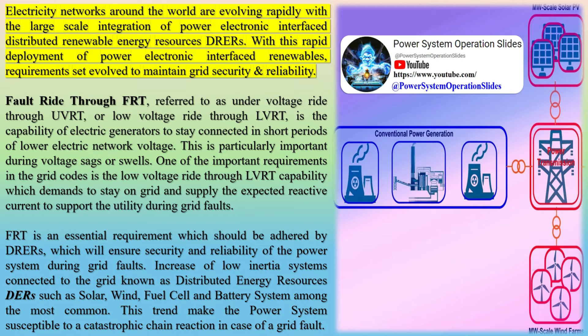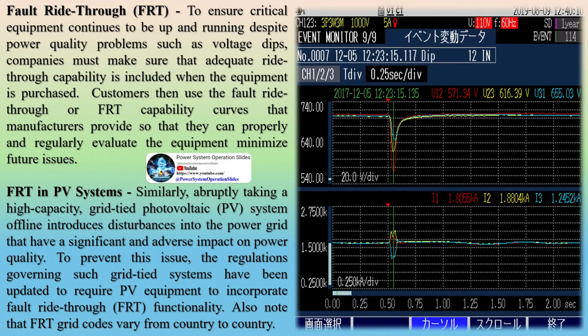Fault Ride-Through (FRT), referred to as Under-Voltage Ride-Through (UVRT) or Low-Voltage Ride-Through (LVRT), is the capability of electric generators to stay connected during short periods of lower electric network voltage. This is particularly important during voltage sags or swells. One of the important requirements in the grid codes is the LVRT capability, which demands staying on grid and supplying the expected reactive current to support the utility during grid faults.